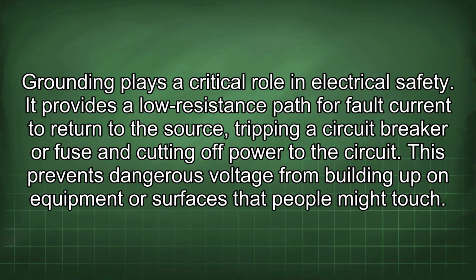Grounding plays a critical role in electrical safety. It provides a low-resistance path for fault current to return to the source, tripping a circuit breaker or fuse and cutting off power to the circuit. This prevents dangerous voltage from building up on equipment or surfaces that people might touch.